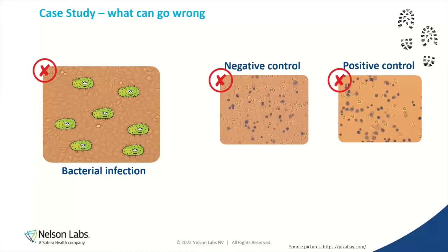Another thing, what a lot of our sponsors do not know is that a cytotox test is performed in batch. So we do a lot of cytotox testing simultaneously. Therefore, if something goes wrong with the complete setup of the testing, all of our sponsors would be affected. And that is something that I've not experienced, that all of a sudden all the sponsors would say, hey, there's something wrong. And that also gives you some guarantee that the testing is under control. And that can also be added in your root cause investigation. When you're in this room checking the validity of the results, you're saying, okay, 100 devices were tested in the same run and only mine is not doing what I want. I am seeing a fail. That can also mean that the testing is under control.